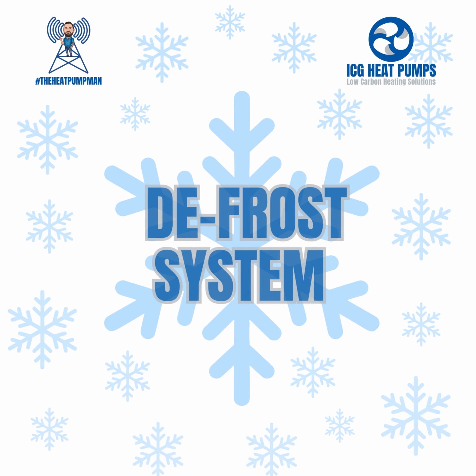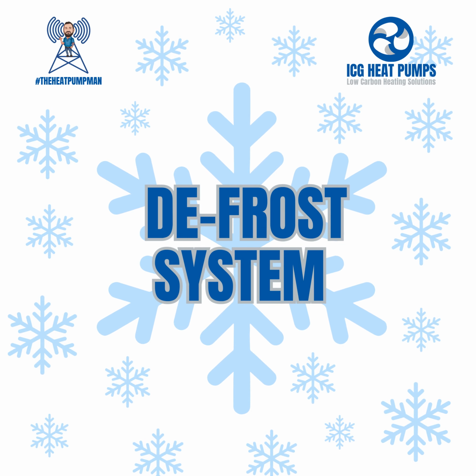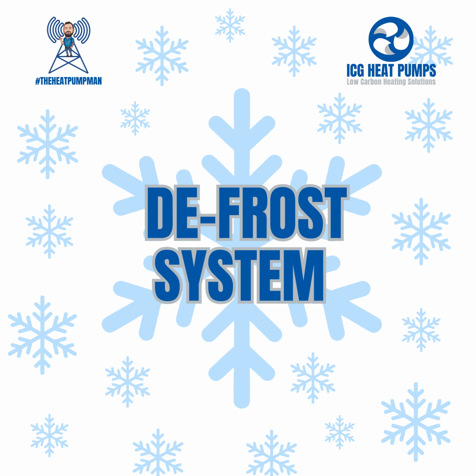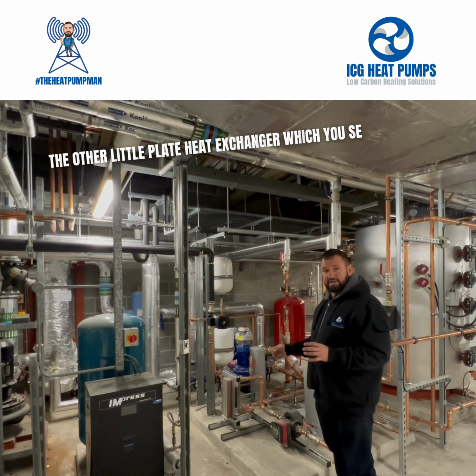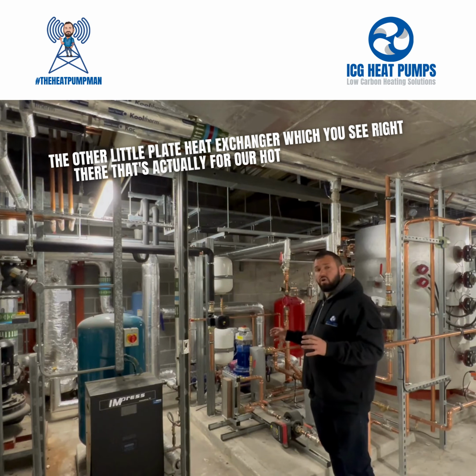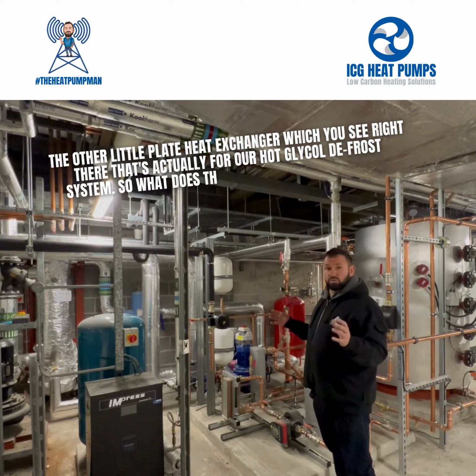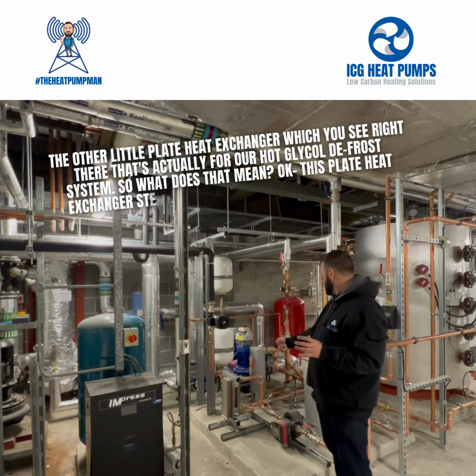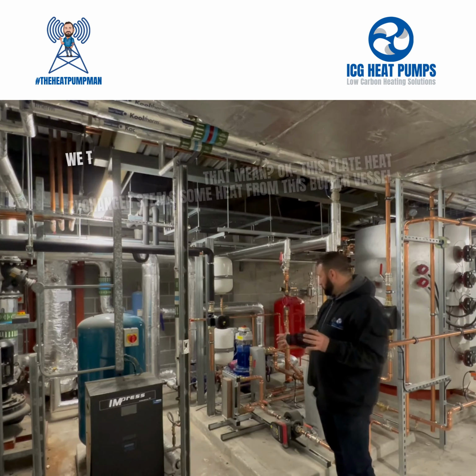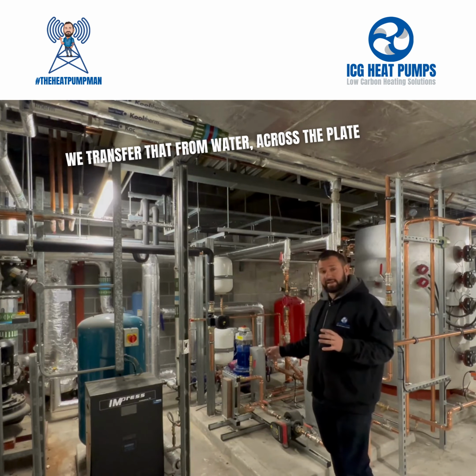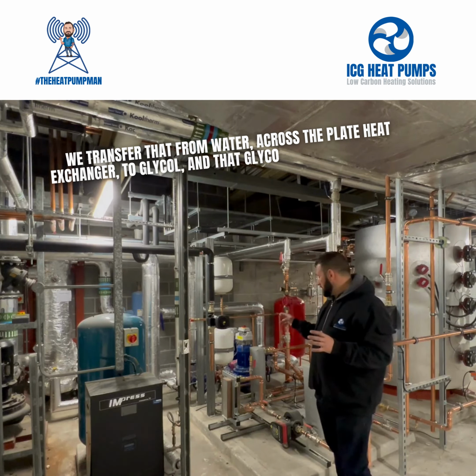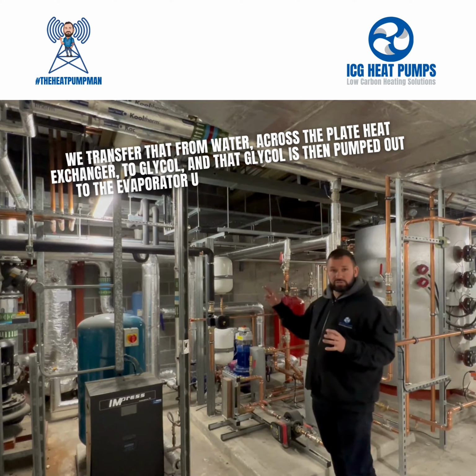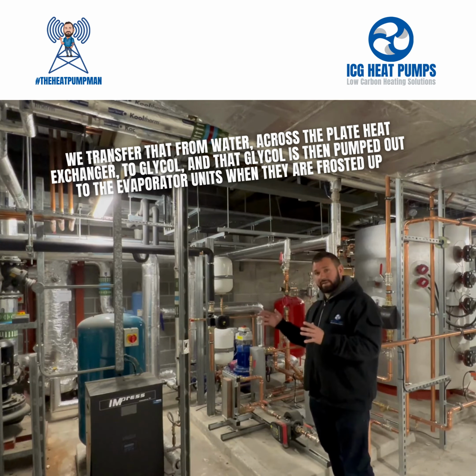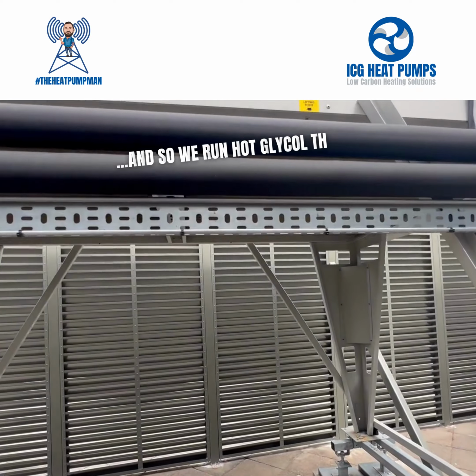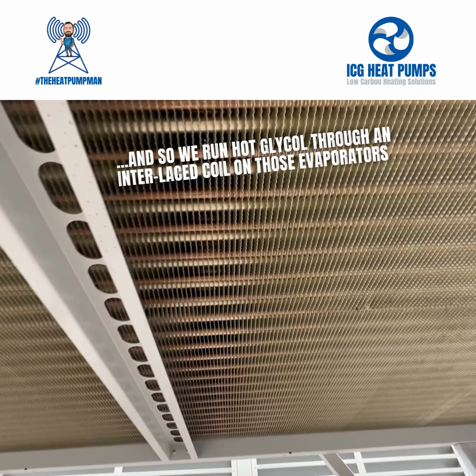When it's cold outside and there's moisture in the air, we will accumulate frost on the coil of the evaporators, and so we need a defrost system. The other little plate heat exchanger which you see right there, that's actually for our hot glycol defrost system. So what does that mean? This plate heat exchanger steals some heat from this buffer vessel, transfers that from water across the plate heat exchanger to glycol, and that glycol is then pumped out to the evaporator units when they are frosted up. So we run hot glycol through an interlaced coil on those evaporators.